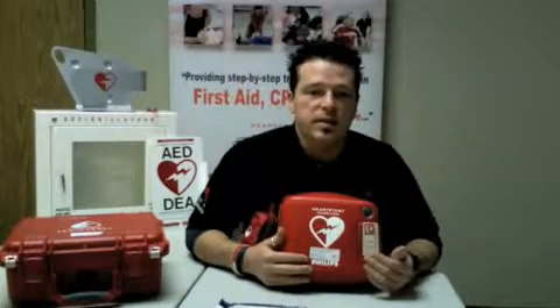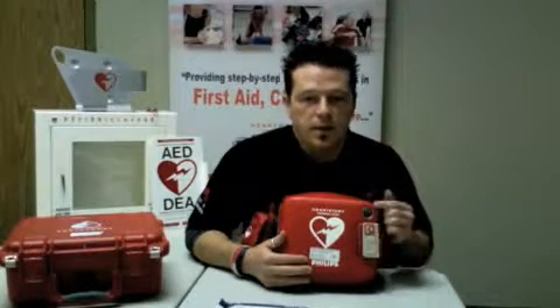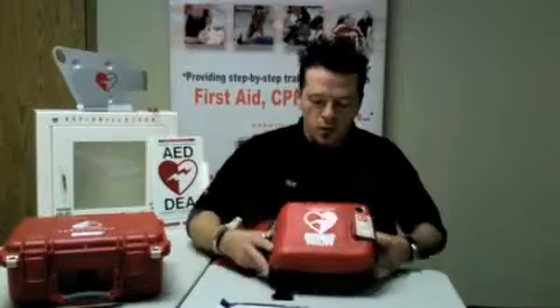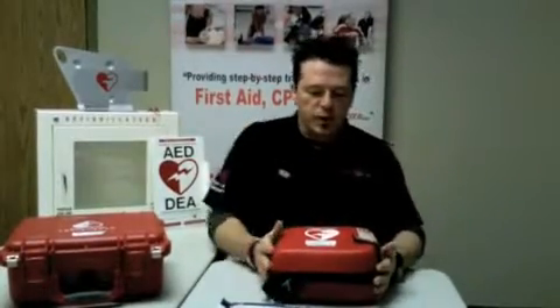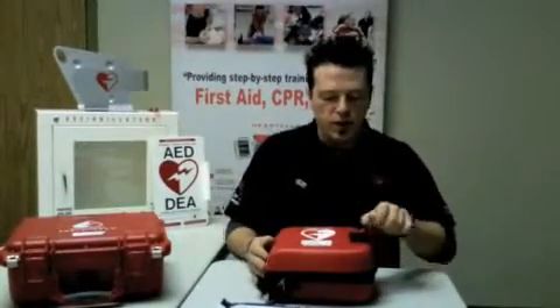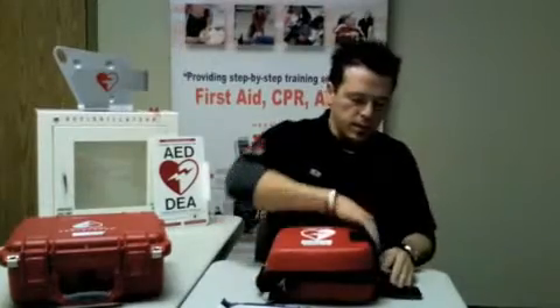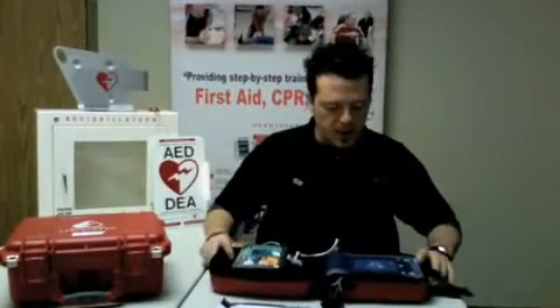When we mean servicing, it means checking to make sure that the battery as well as the defibrillator itself are in working order, as well as the consistency of the electrode pads, so they are ready to be used. Again, if this little flickering green light is not present, that means that the servicing is mandatory. Now, to access the defibrillator from the soft case, just take off the Velcro and open up the casing.